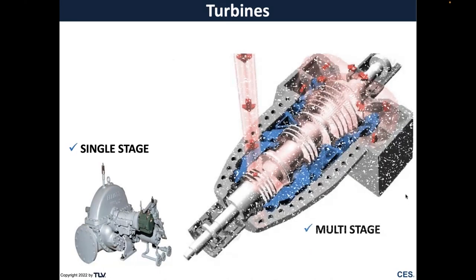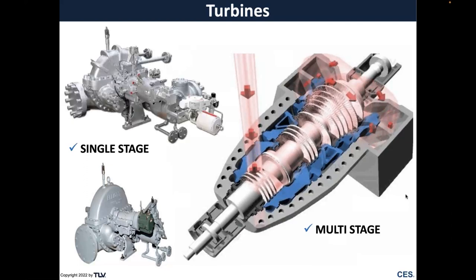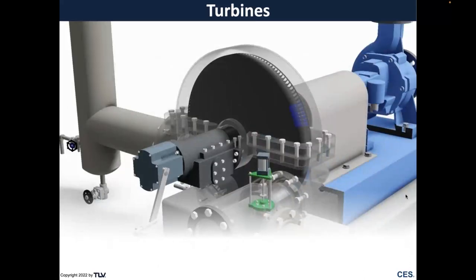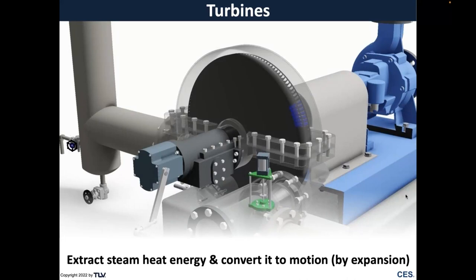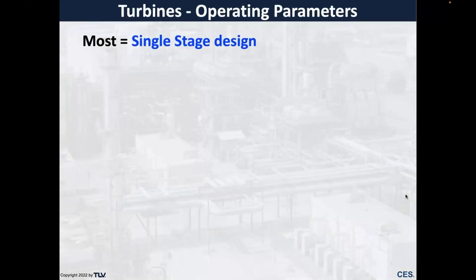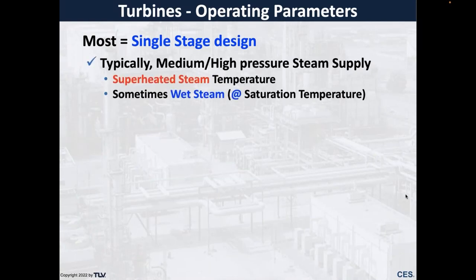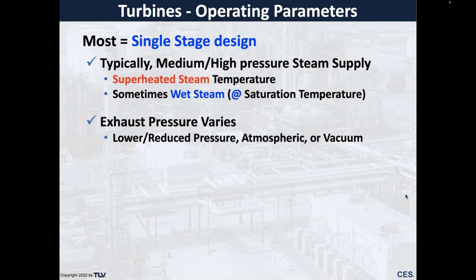Let's talk about single-stage turbines and multi-stage turbines. Even single-stage turbines can be rather sophisticated. We want to extract heat energy and convert it to motion by expansion. This is important to distillation because turbines are used in so many distillation operations, and your distillation assets will not perform if their turbines are not running properly. Most turbines we deal with are single-stage design, typically medium or high pressure steam supply including superheated steam, but sometimes we have wet steam. Exhaust pressure can vary from reduced pressure to atmosphere or vacuum.